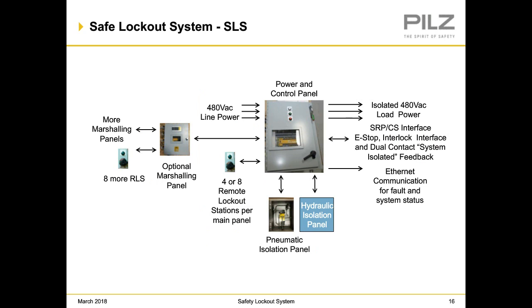So here's another picture of that similar concept with some actual pictures of remote lockout stations. Again, on the left, it shows eight lockout stations going into a marshaling panel, and the main unit, the power and control panel, can handle either four or eight remote lockout stations depending on the size of the unit. And you can see here the 480 volt power coming in and then the isolated or load power going out. And again, we have a couple slides coming up that will show this even better. And then you have your pneumatic isolation panels or hydraulic isolation panels. As well, you have Ethernet communication for fault and system status. And this can be Modbus TCP, Ethernet IP, several different industrial communication networks.